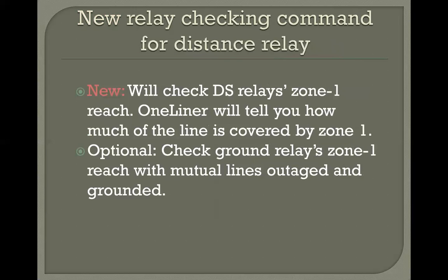Now, one thing you might already have thought of when I was describing the existing commands: how come there is nothing there for checking distance relays? Well, we're going to make that up in this new version. The new command will check distance zone 1 and zone 2 reaches. This slide is about zone 1. The new command will check the distance relay zone 1 reach and tell you how much of the line is actually covered by zone 1.